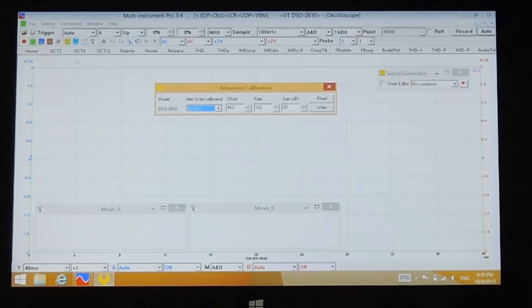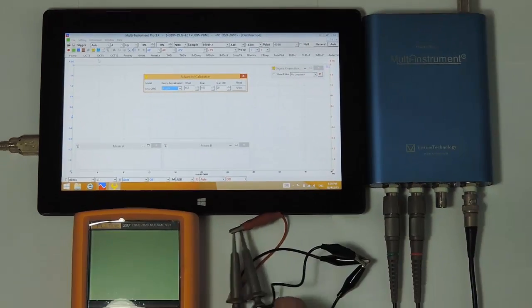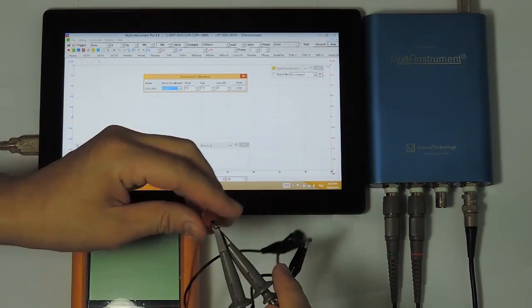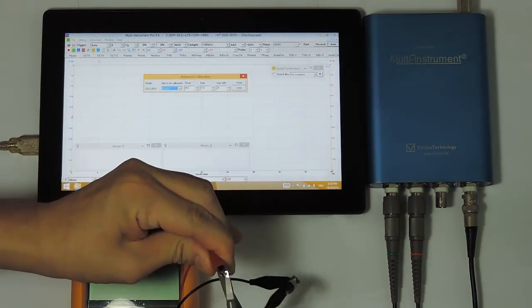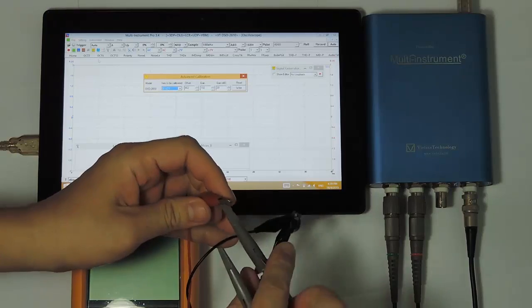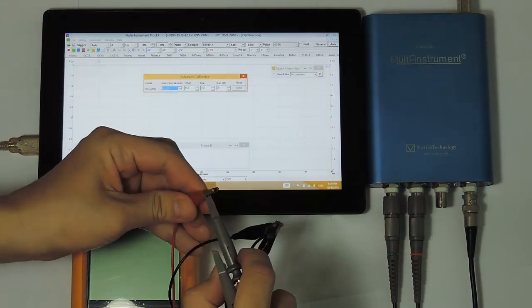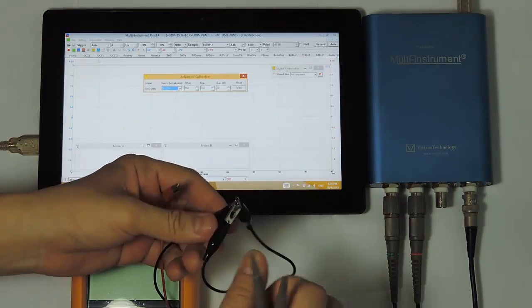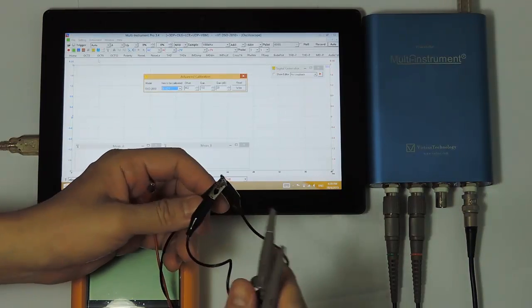We do offset calibration first, so connect each probe tip to its ground lead to short the input to the ground.